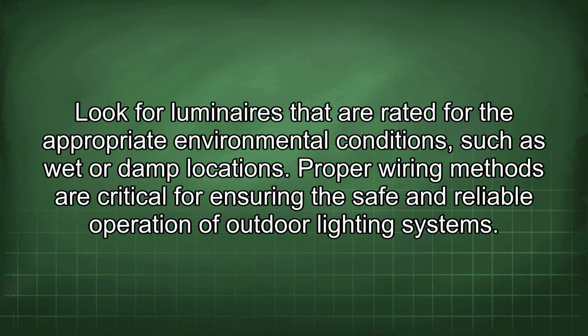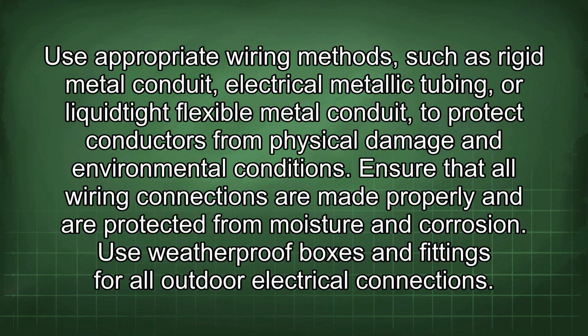Proper wiring methods are critical for ensuring the safe and reliable operation of outdoor lighting systems. Use appropriate wiring methods, such as rigid metal conduit, electrical metallic tubing, or liquidtight flexible metal conduit to protect conductors from physical damage and environmental conditions. Ensure that all wiring connections are made properly and are protected from moisture and corrosion. Use weatherproof boxes and fittings for all outdoor electrical connections.